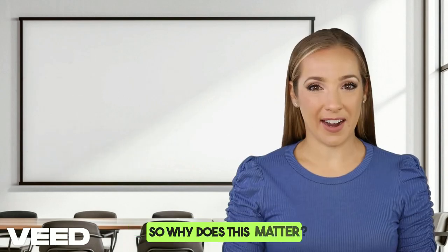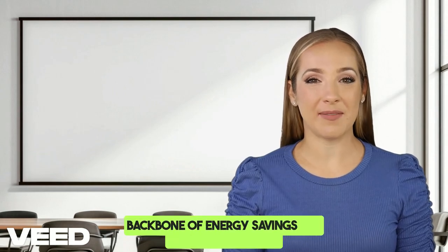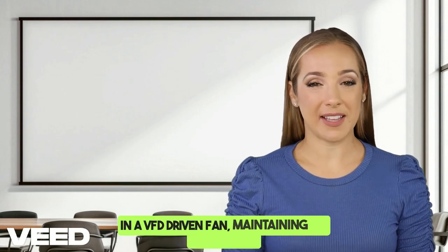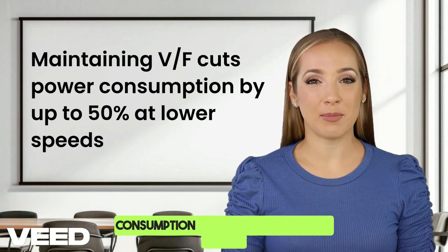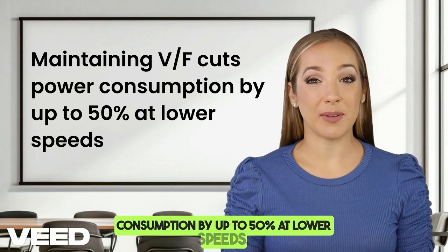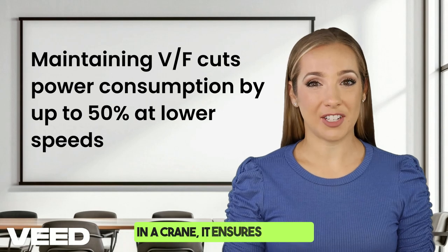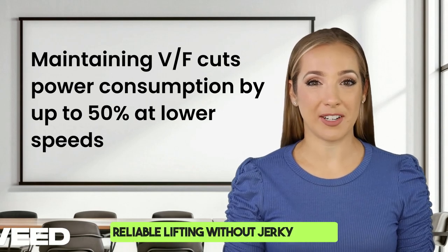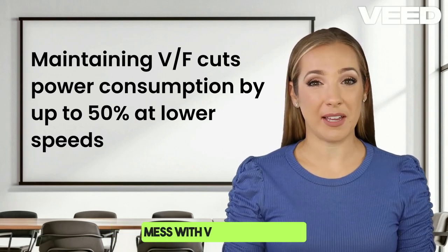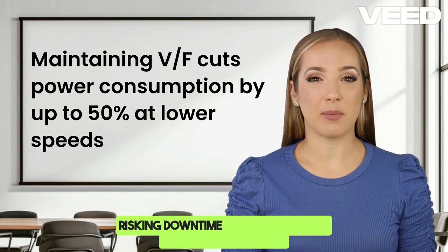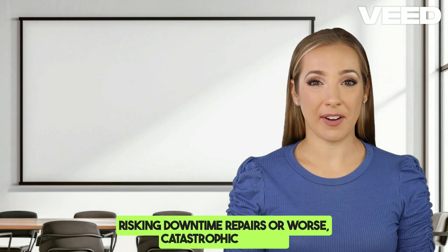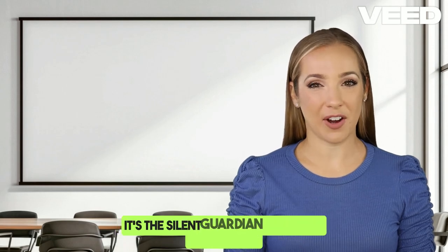So, why does this matter? The V by F ratio is the backbone of energy savings and precision control. In a VFD-driven fan, maintaining V by F cuts power consumption by up to 50% at lower speeds. In a crane, it ensures smooth, reliable lifting without jerky starts. Mess with V by F, and you're risking downtime, repairs, or worse, catastrophic failure. It's the silent guardian of modern automation.